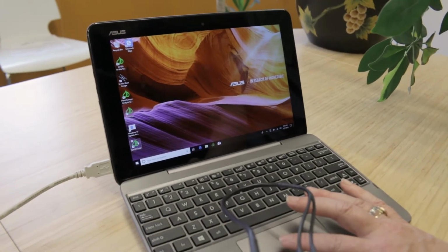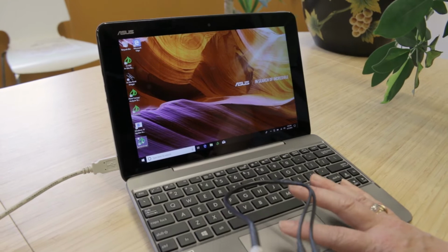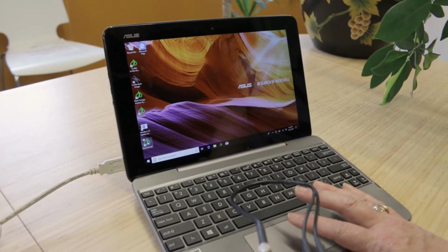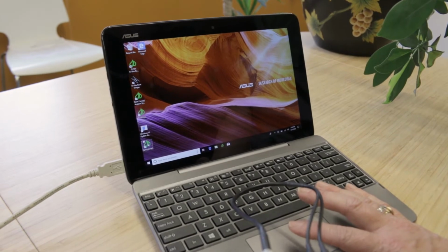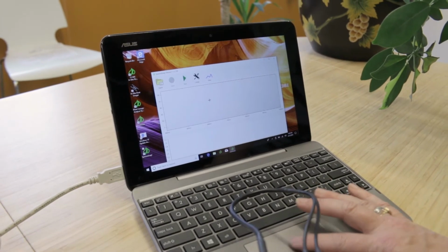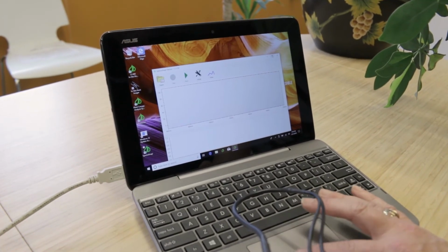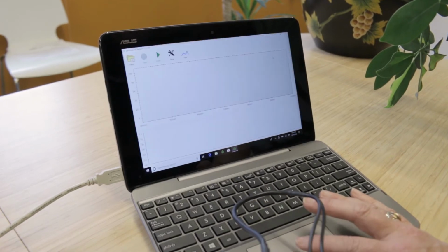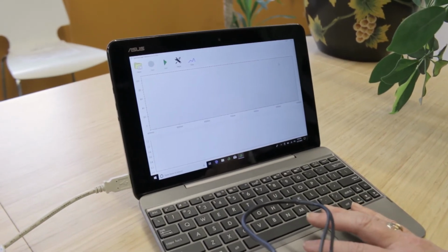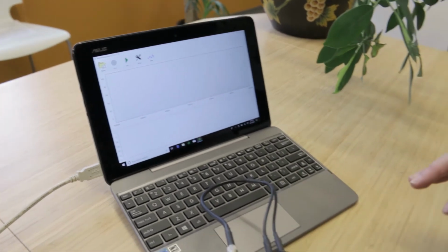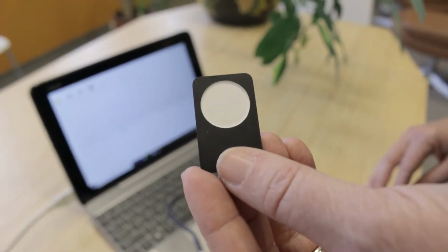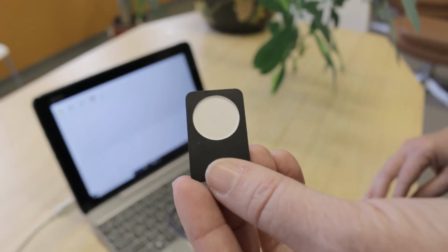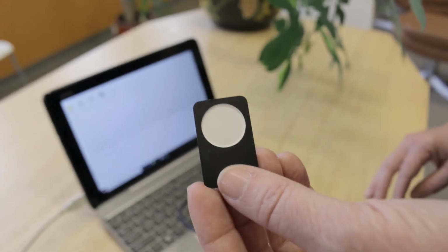Open the SpectroSnap software using the icon. It takes just a minute to load. I like to expand it to full screen. Before you begin any measurements, you'll want to use the included reflectance standard to calibrate the instrument. Simple instructions are in the manual.